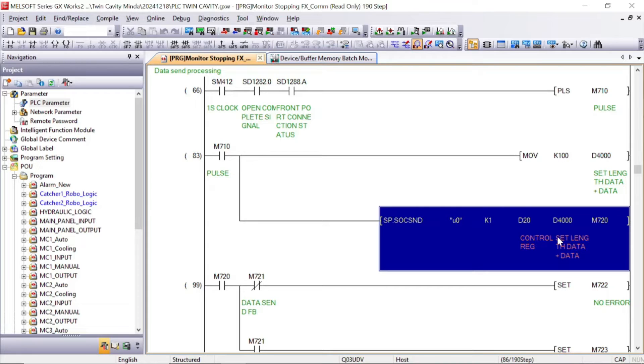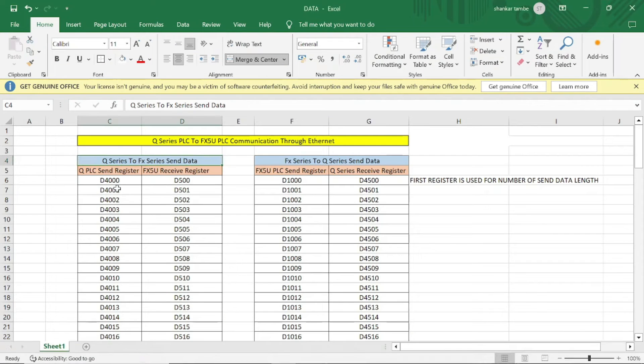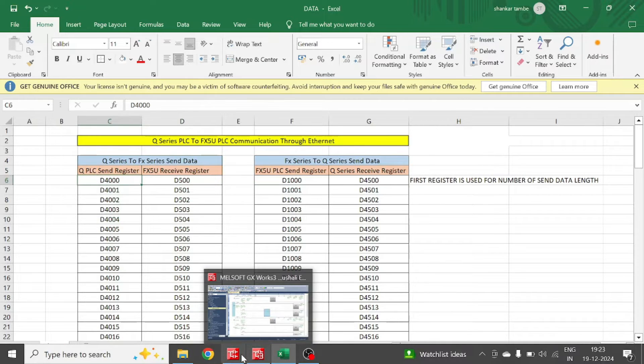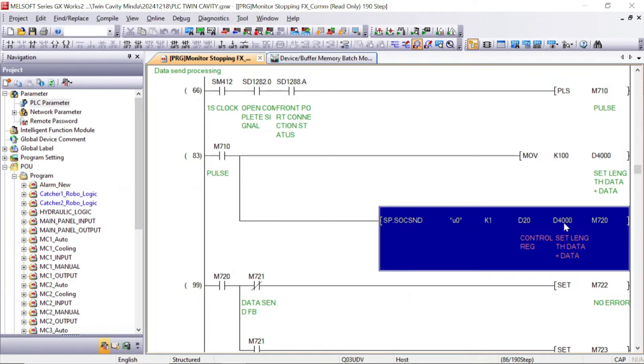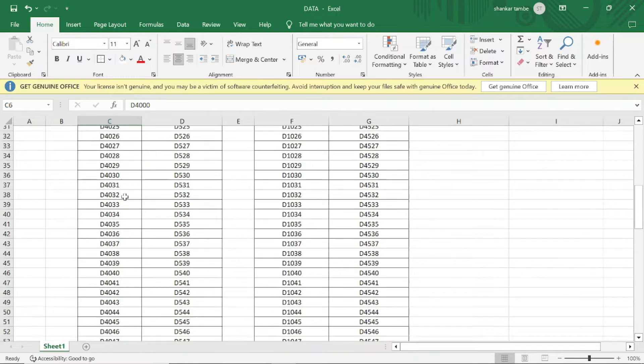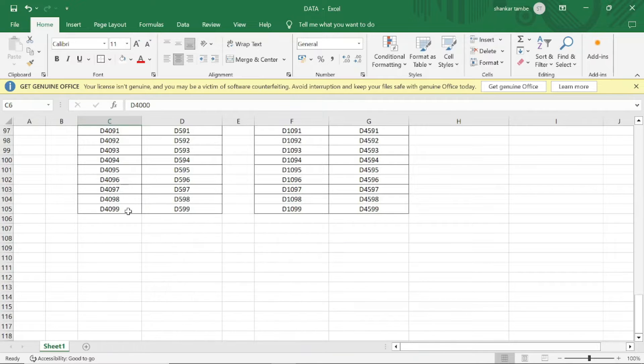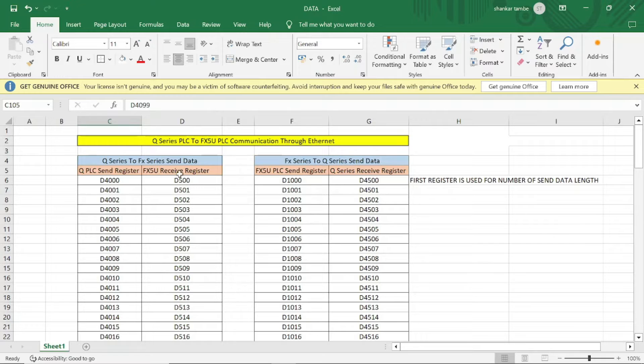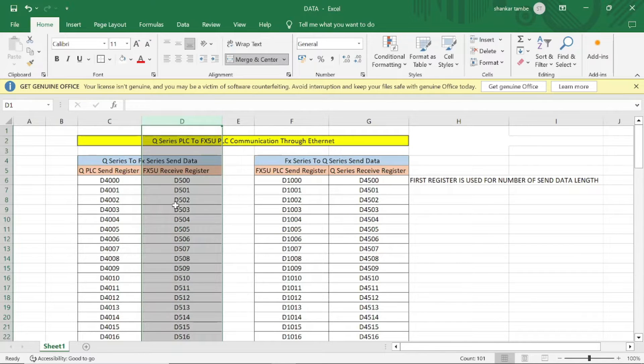In this list I will show you Q series to FX series send data. In Q series we have written D4000 in the send instruction — this is our socket send instruction. From D4000, 100 registers up to D4099, the 100 registers will be overwritten in the FX5U PLC.